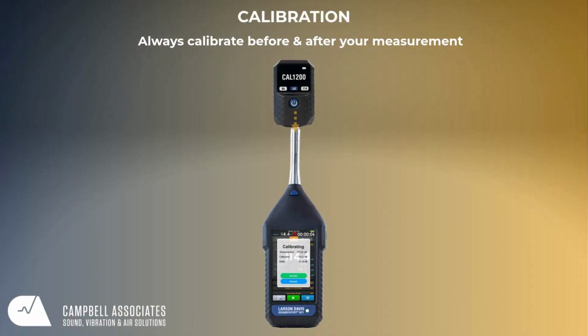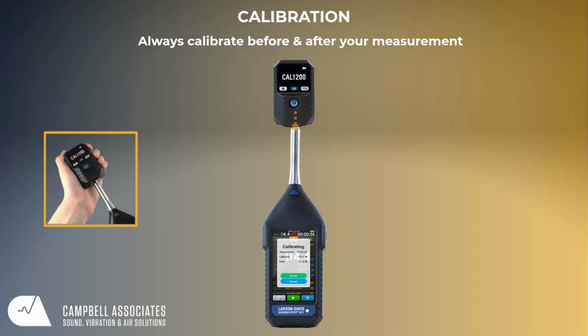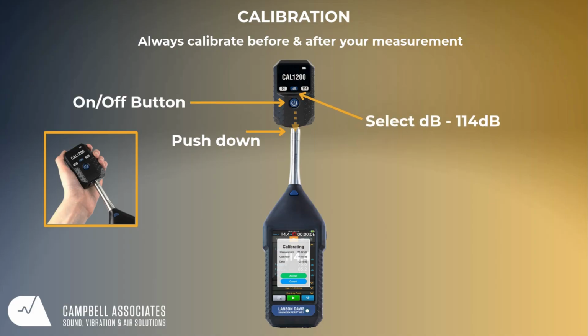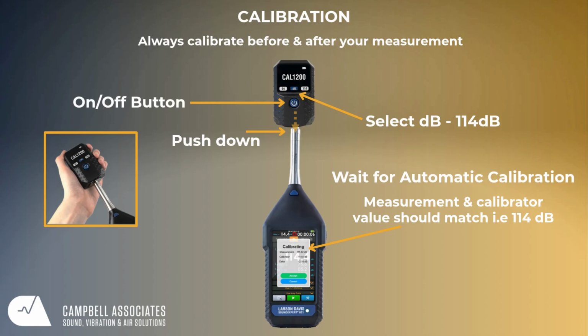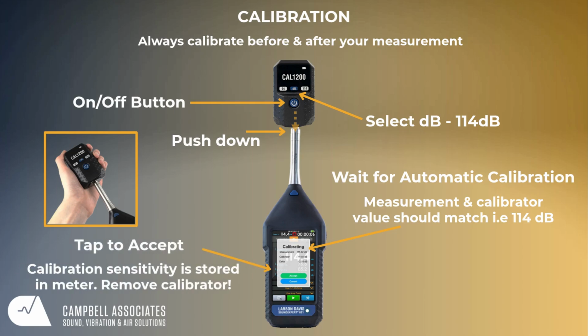Before you start your measurement, you need to do a field calibration. This is recommended before and after your measurement. To start the calibration process, put your field calibrator on the end of the microphone and press the on button. Make sure your calibrator is set to 114 dB. Once the calibrator is on, wait for a few seconds until the calibration screen pops up. The meter will start the calibration process automatically, and once it's finished, the accept option will appear on screen. If you're happy with the calibration results, press accept.